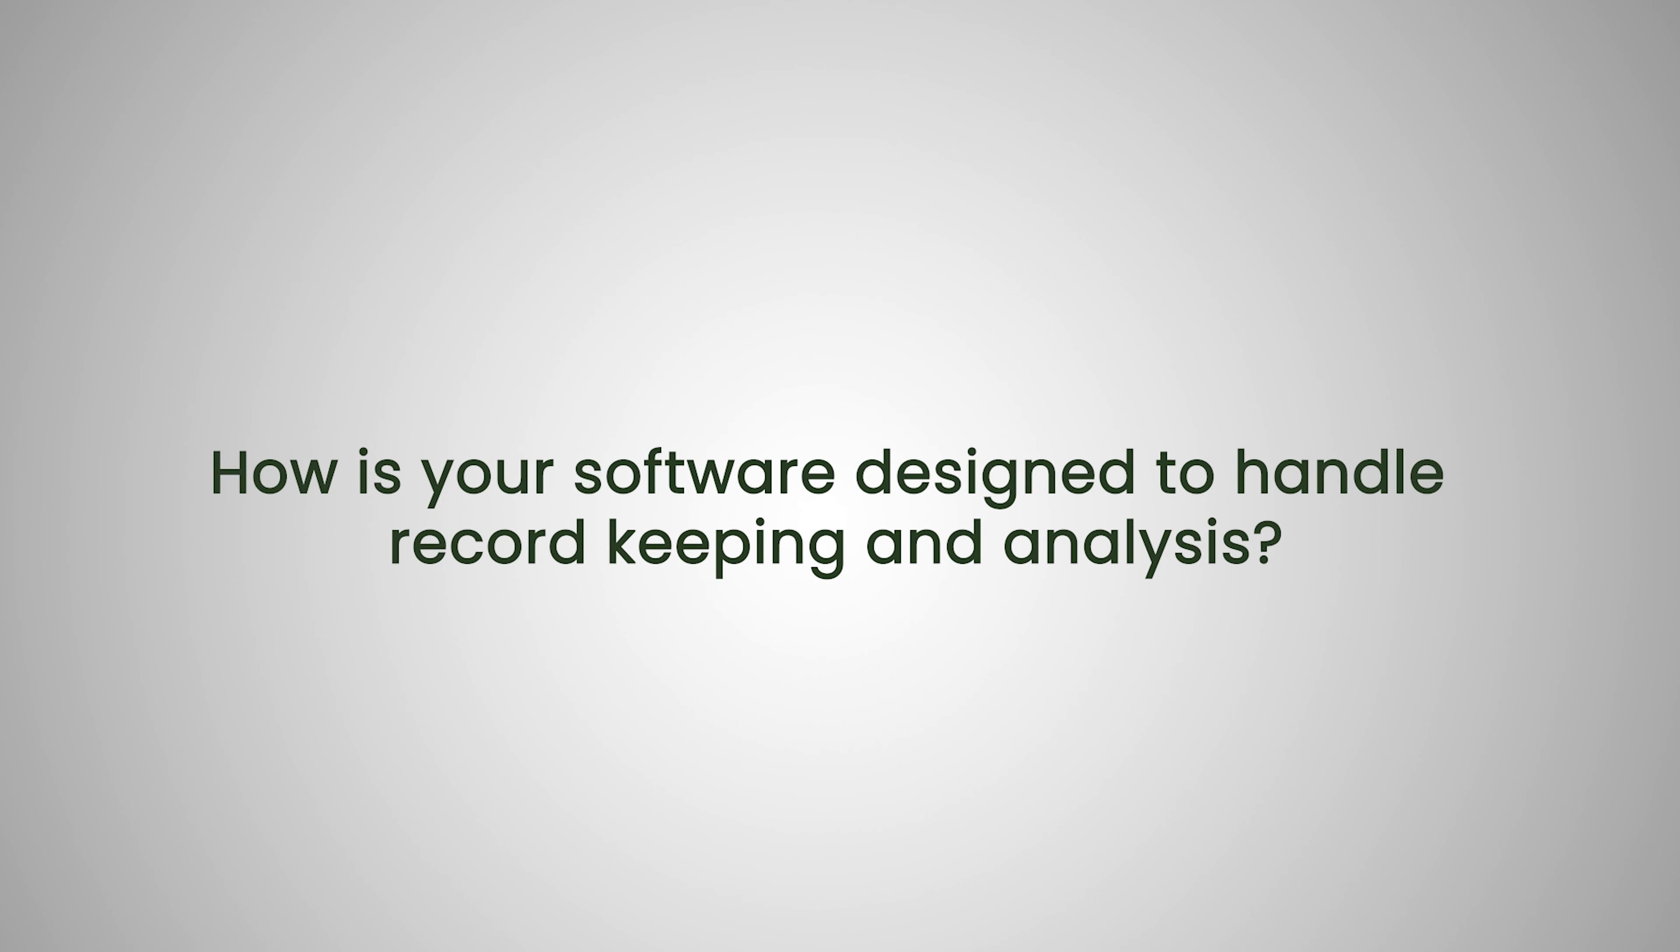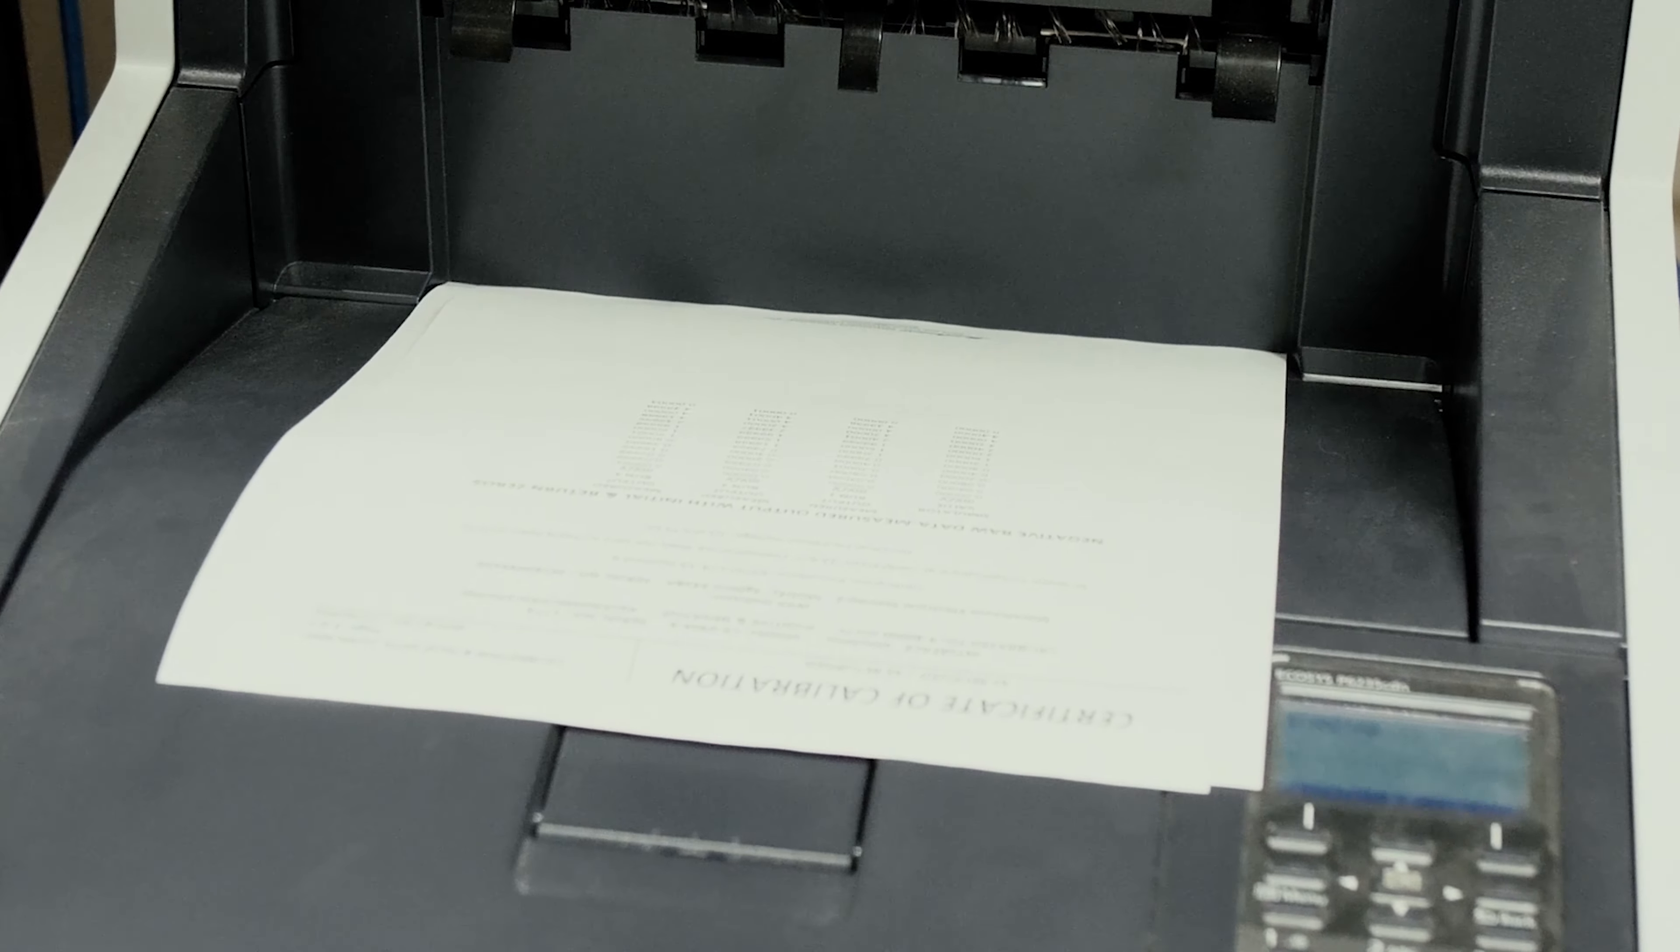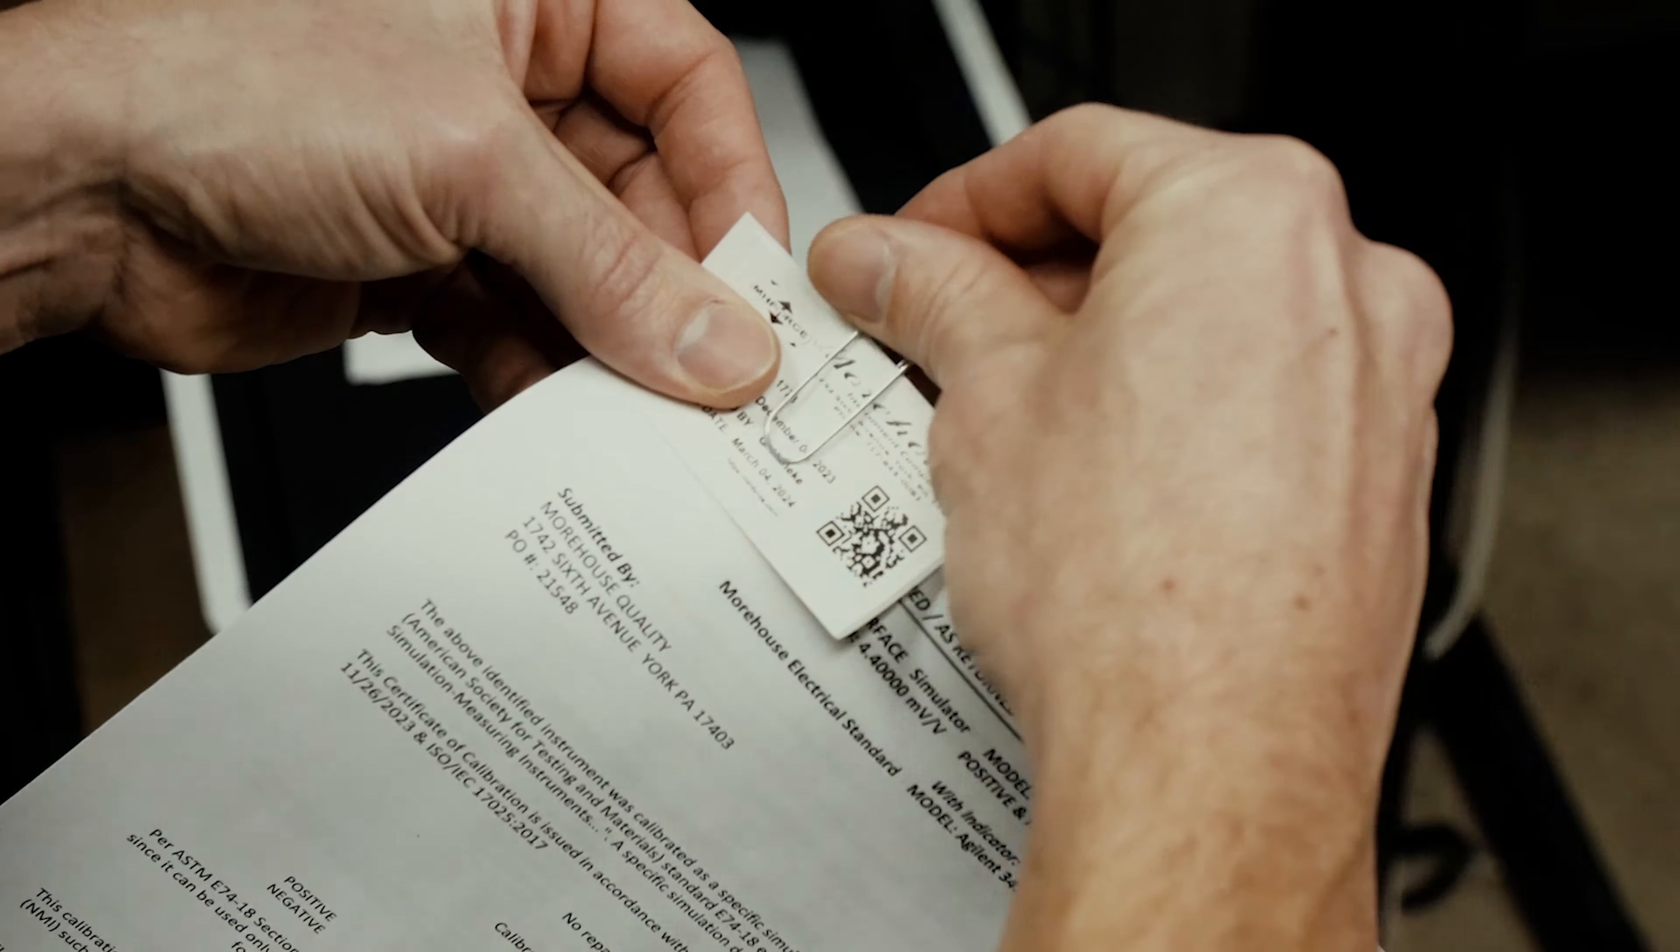How is your software designed to handle record keeping and analysis? So the software captures all the data automatically and then you can use that to generate certificates for ASTM E74, ISO 376 or various decision rules like ANSI Z540.3, Method 5 or 6, ILAC G8 and others.